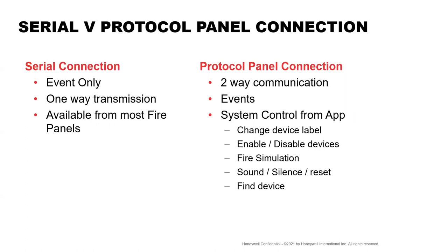If there's issues on a device and it's gone into fault and you need to change it, you can disable it for a while. If you've got hot or cold works going on, you can disable a device so the hot works can go on without setting the system into fire. When the works have been done and you've confirmed that that's all back to normal, you can then re-enable without having to go to the fire panel. So you can do it remotely.